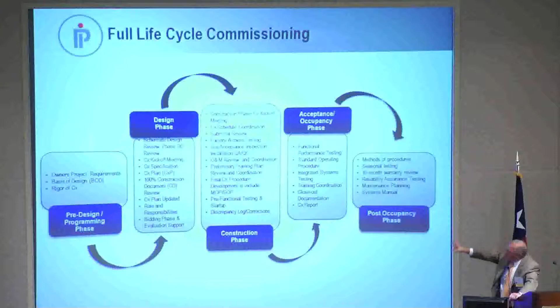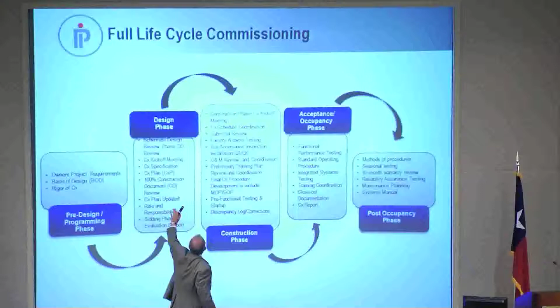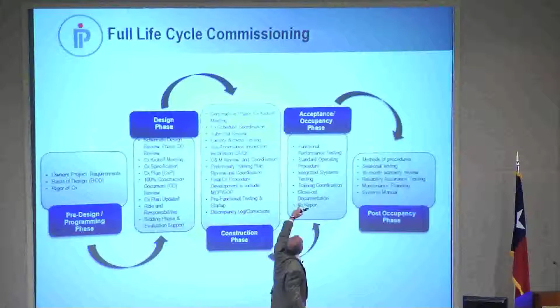One thing I want to stress is that a lot of your operational elements - developing maintenance operations procedures, standard operating procedures, O&M review and coordination - should be fully planned and vetted at the end of the design phase, validated and incorporated into the construction phase, and fully vetted during the acceptance phase.